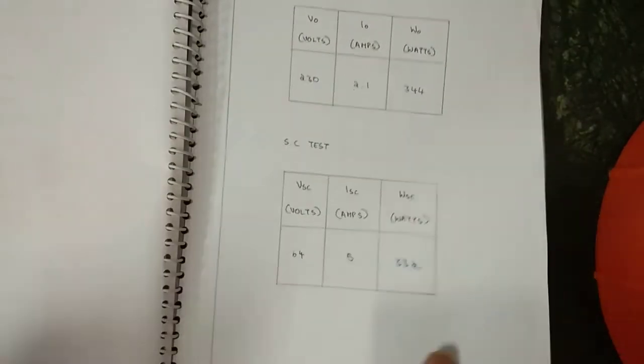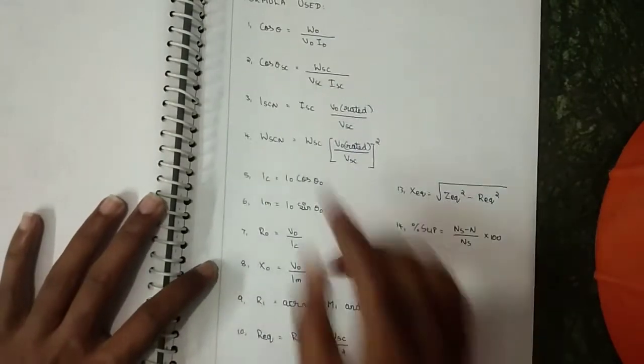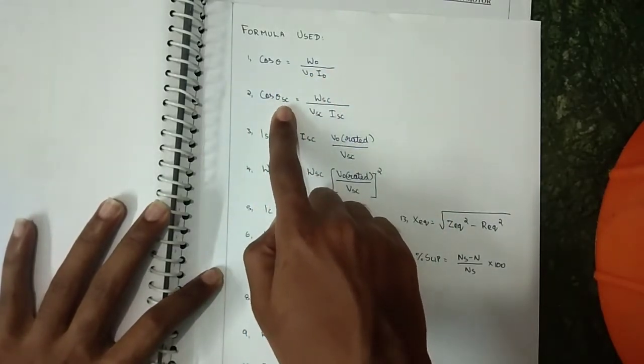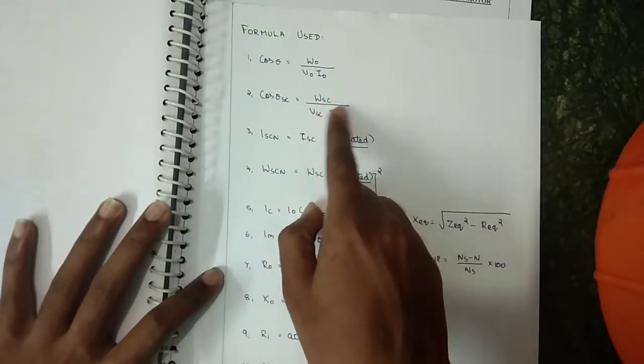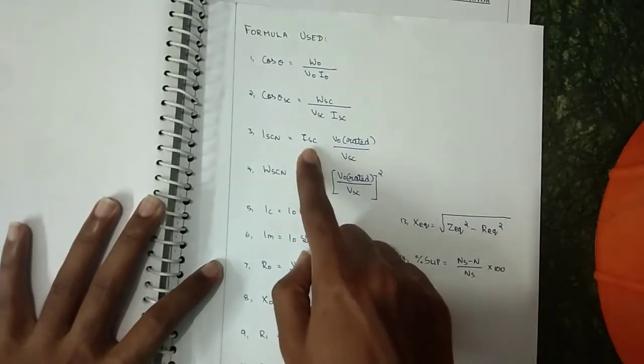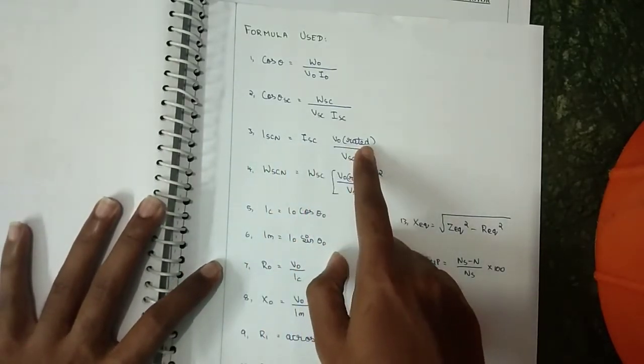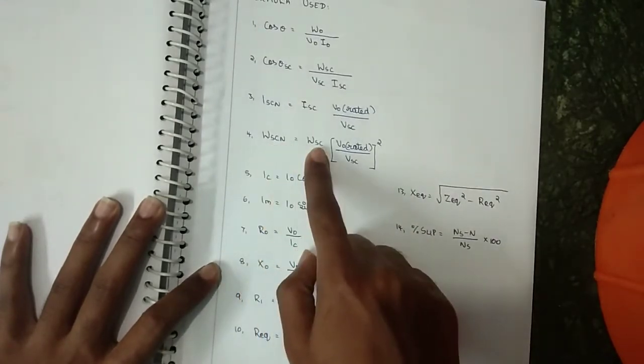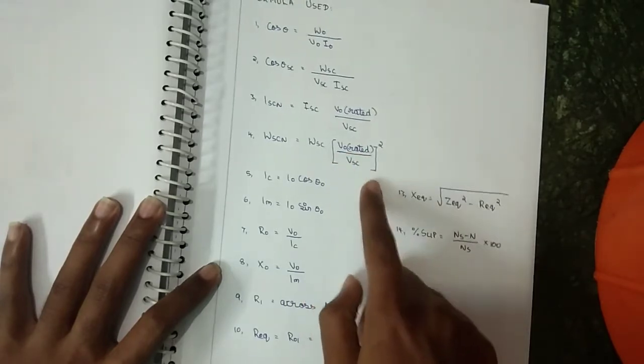The formulas for the whole experiment are: cos θ₀ = W₀ / (V₀ × I₀); cos θ_SC (power factor at short circuit) = W_SC / (V_SC × I_SC); I_SC_rated = I_SC × (V₀_rated / V_SC); and W_SC_normalized = W_SC × (V₀_rated / V_SC)².